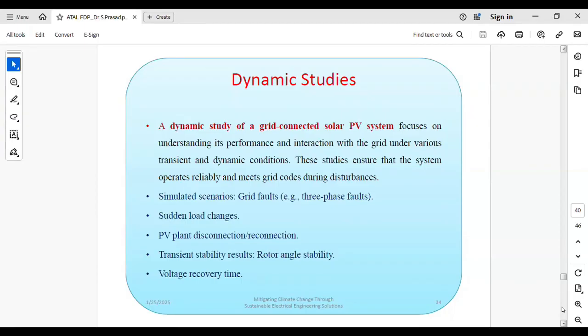By conducting the test using DIgSILENT PowerFactory or ETAP software, you can determine the clearing time when a fault happens, that is, at what time your breaker has to open so that the fault is removed from the system. That is why we conduct transient stability analysis, to know the operation time of the breaker, and this time will also be used in relay coordination. So all are interlinked. At what time we need to clear the fault so that the generators at the existing plant remain stable will be determined by conducting this test.